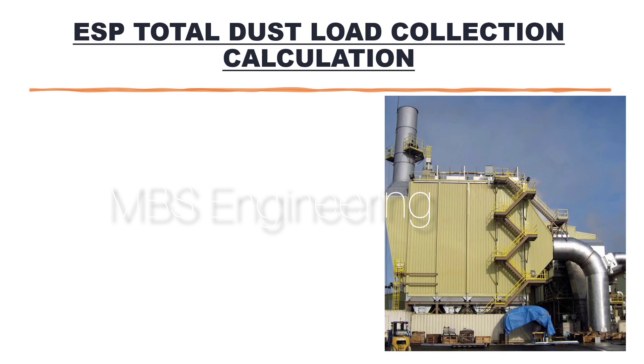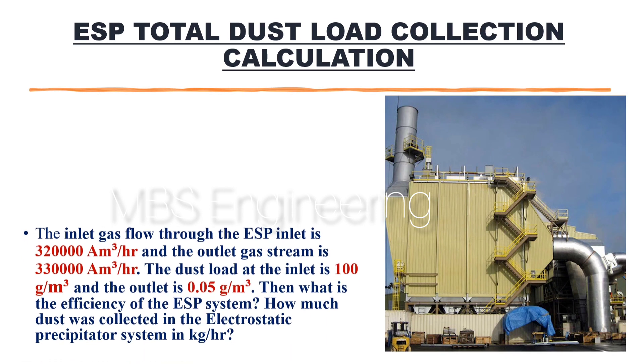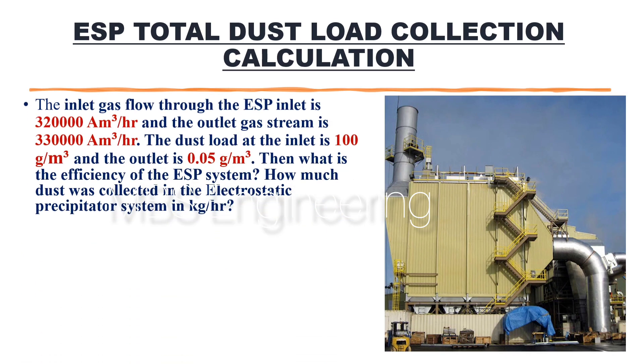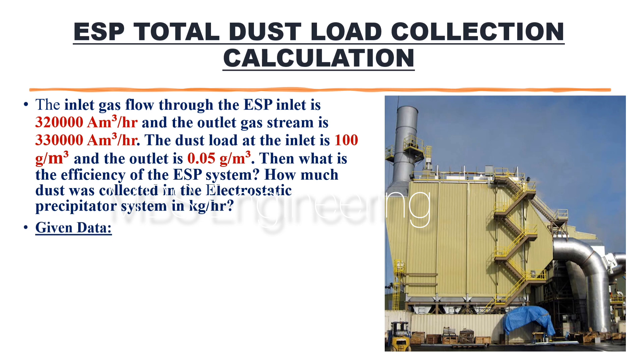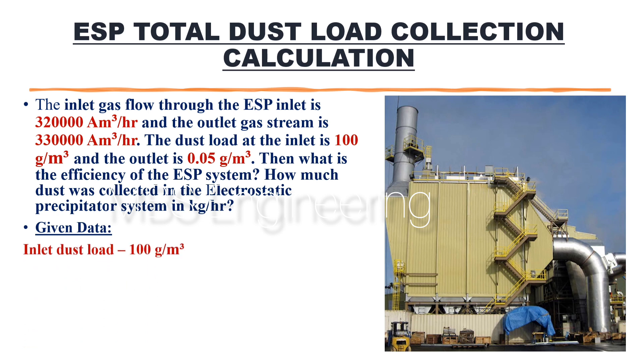We will look at the ESP total dust load collection calculation for a better understanding. The inlet gas flow through the ESP is 3,20,000 cubic meters per hour and the outlet gas stream is 3,30,000 cubic meters per hour. The dust load at the inlet is 100 grams per cubic meter and at the outlet is 0.05 grams per cubic meter. Then, what is the efficiency of the ESP system, and how much dust was collected in kilograms per hour?